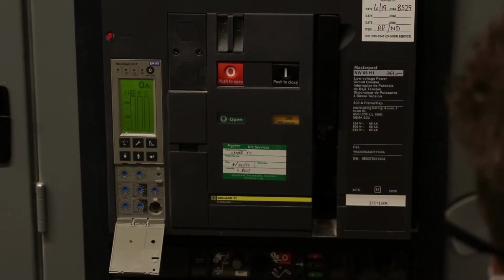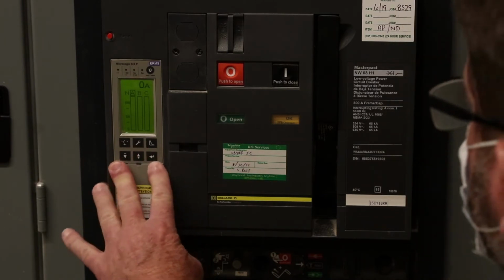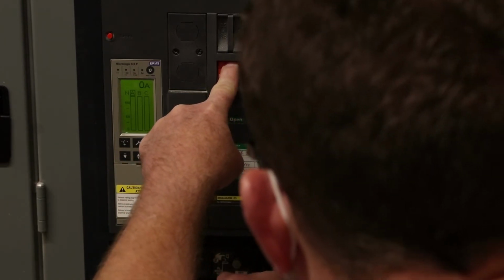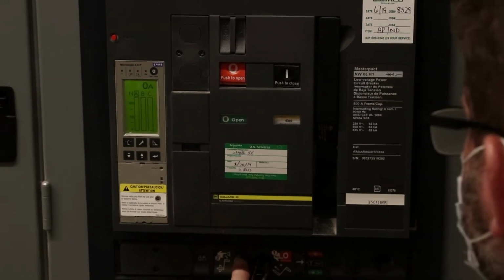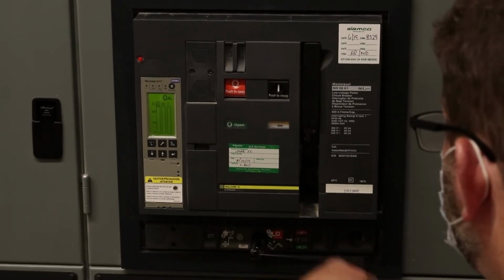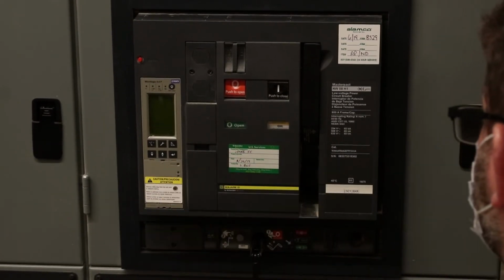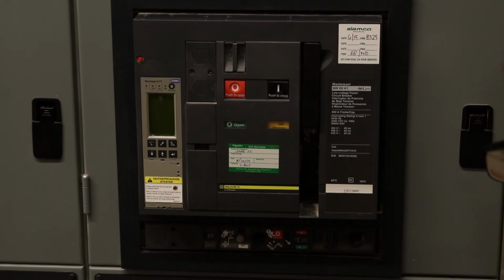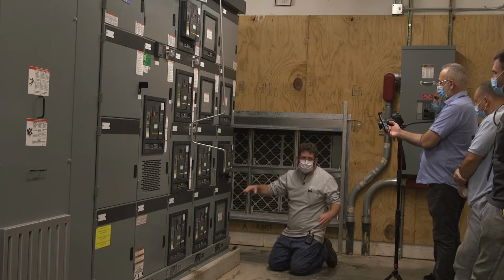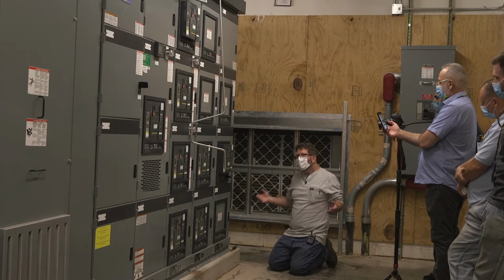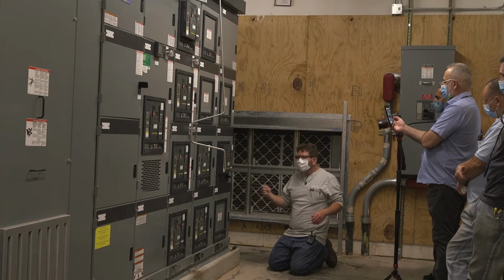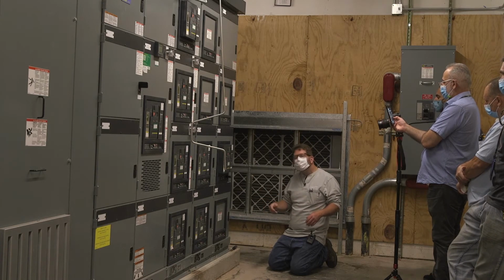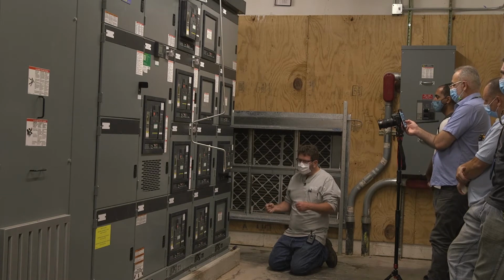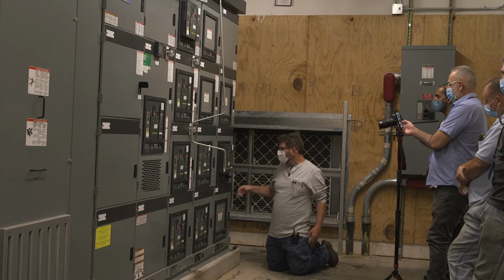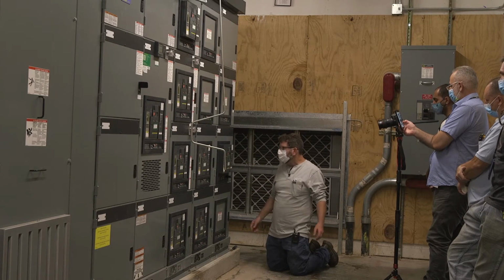To rack the breaker out, same idea. Push and hold the open button. Install the crank. Push the gray button. Bring it out. And when you get to any of these positions, once the button pops out, you're in that position. You can just stop racking. With older style draw-out breakers, it was kind of a feel when you thought it was in far enough, which led to a lot of people really torquing breakers in, causing problems with the cell. This, when the button pops out, you're in the position, you're done.